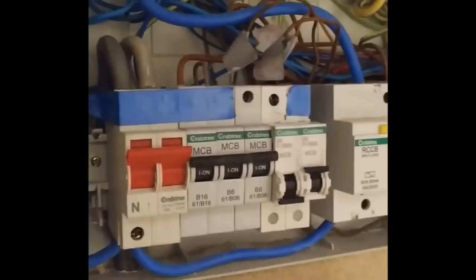Now let's have a look at the installation. This is a bit of video taken on a mobile phone, so it's not very good. But basically we've got two lighting circuits here, and we're going to call these A and B. A on the left, B on the right, both 6 amps. The circuit breakers are actually a different design here, because for some reason a couple of them have been replaced. Again no documentation or information on why that is. Nevertheless there's two circuits, and it's supposed to be one for the ground floor, and another one for the first and the floors above that.